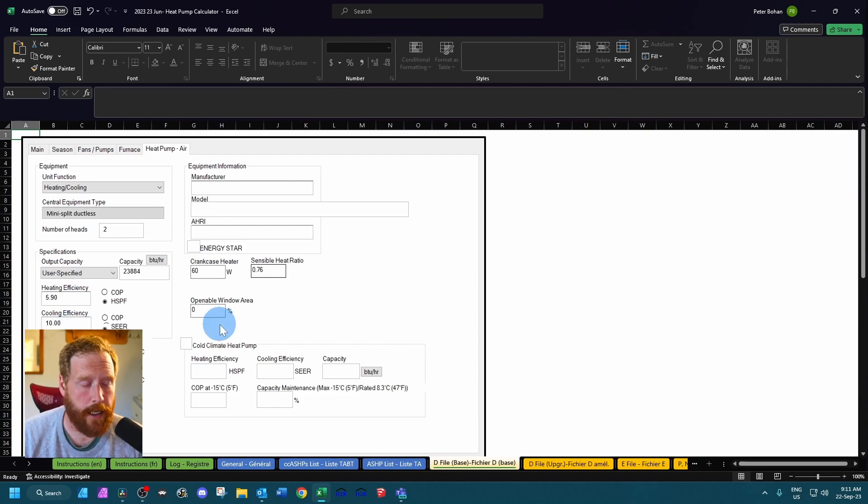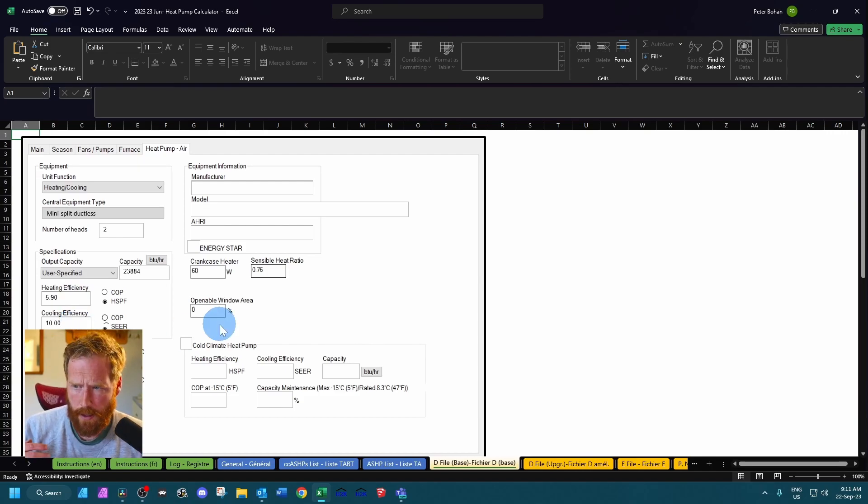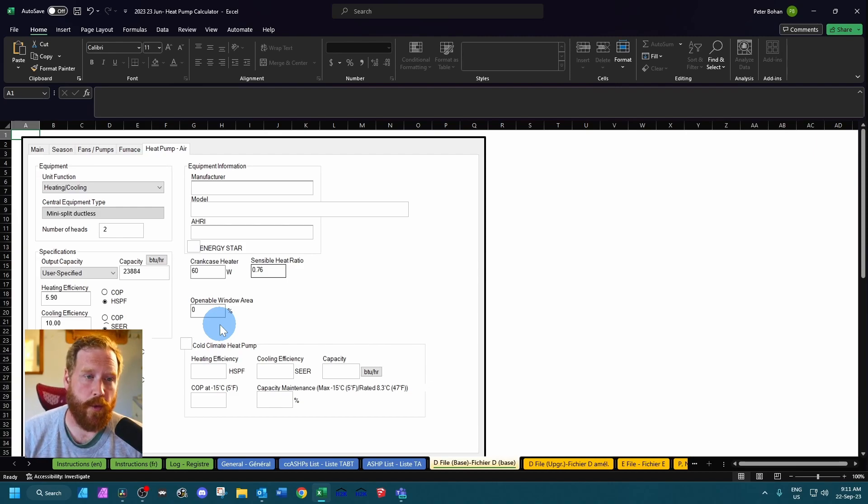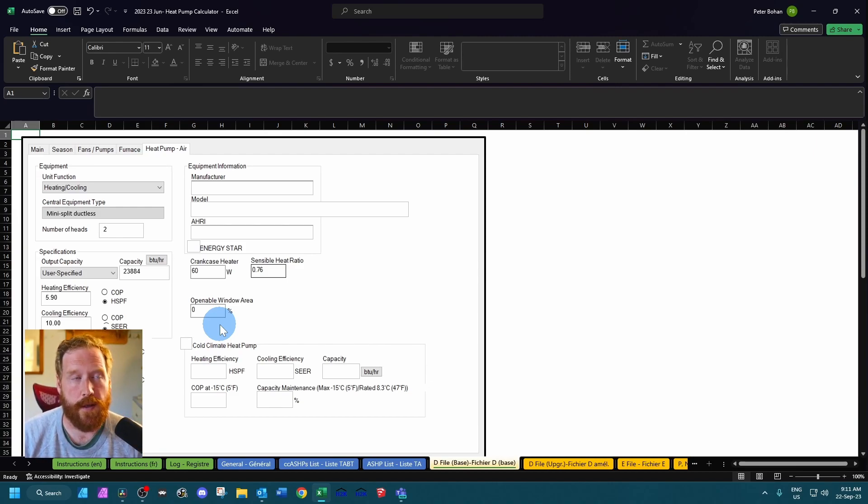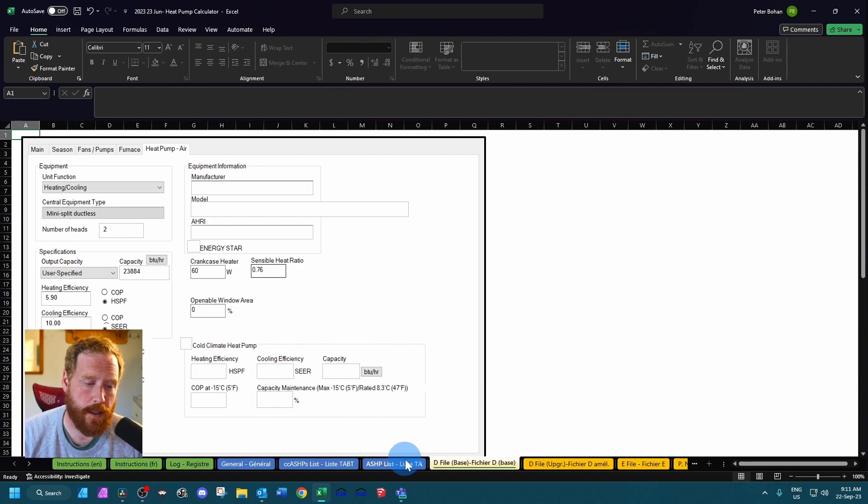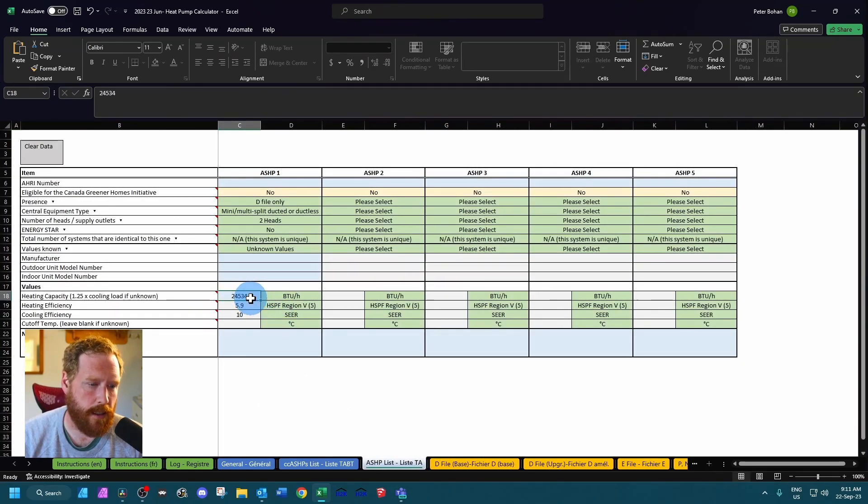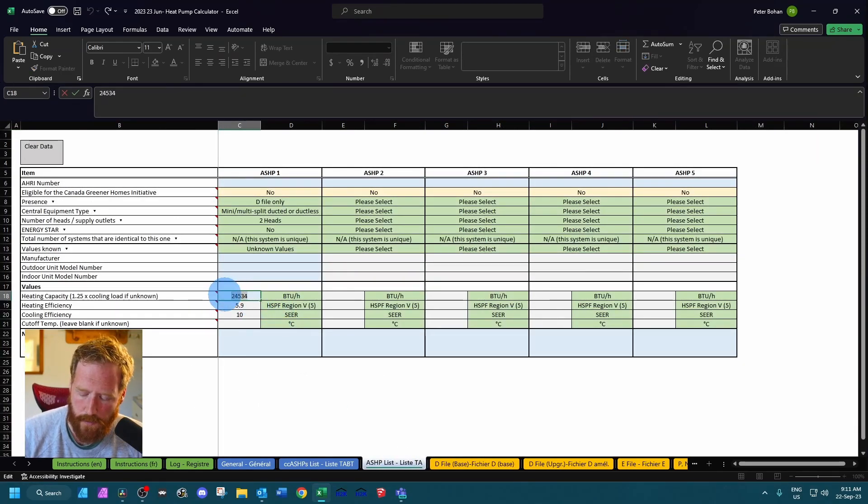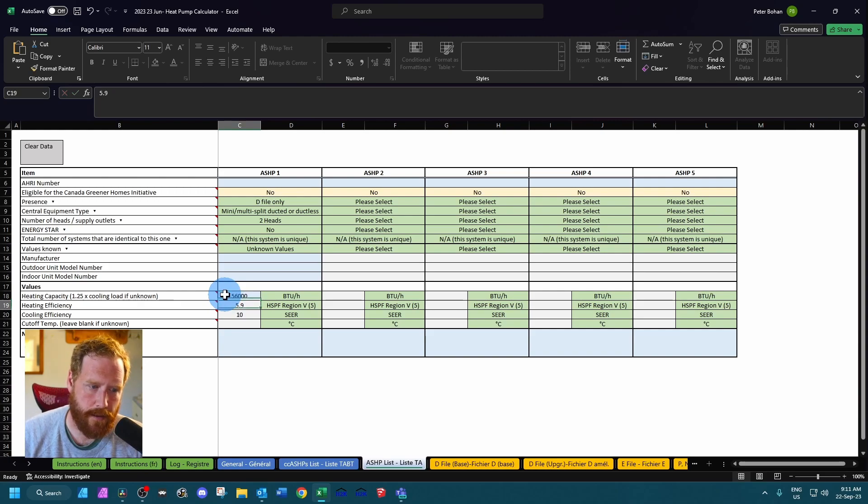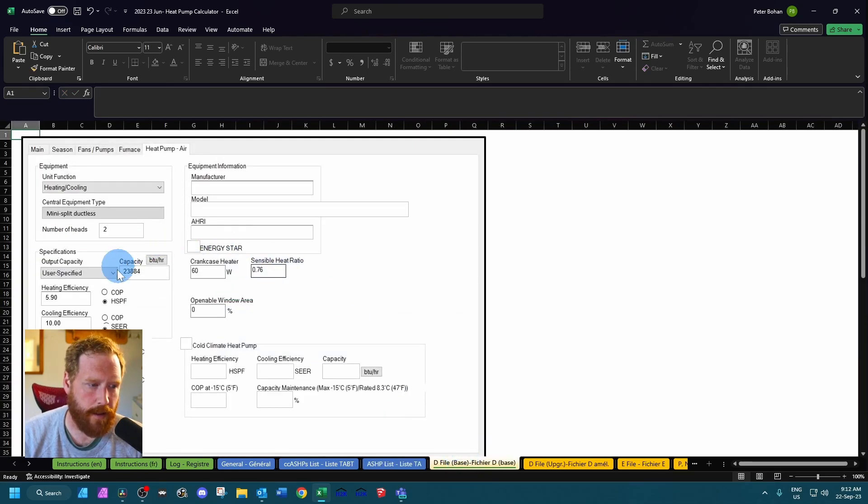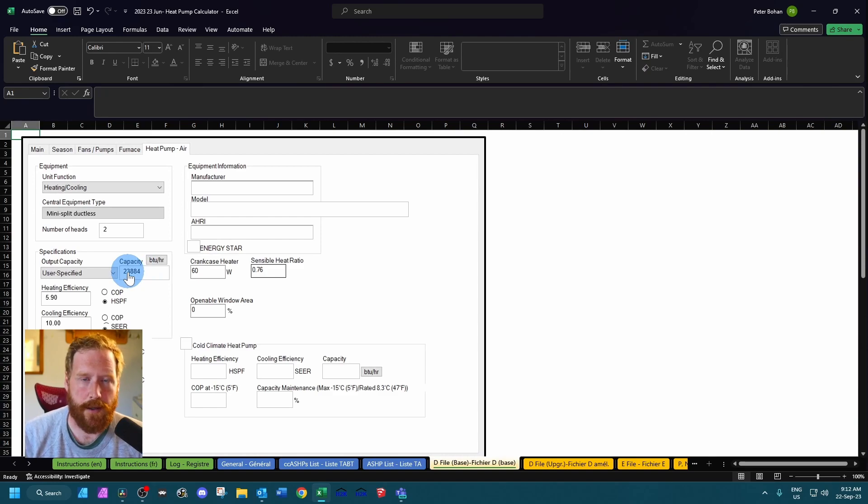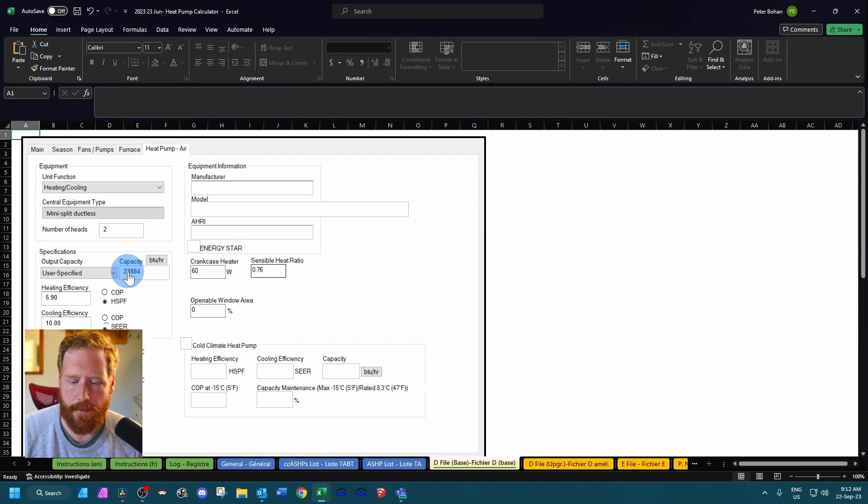One thing to note: in the ERS it does say that when you model an unknown heat pump and you do the 1.25 times cooling load, if it's above 24,000 you need to reduce it to 24,000. But you'll see here it's built into the calculator. So if I was to say that this is 56,000 BTUs per hour and I go back to my d-file, it's the same capacity. So you don't have to worry about it here in this case. And that's everything you need to know with the heat pump calculator. So if you have any questions or comments, feel free to leave them below and I will catch you next time.